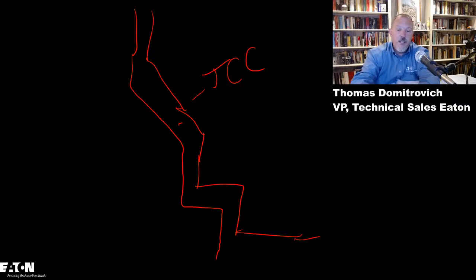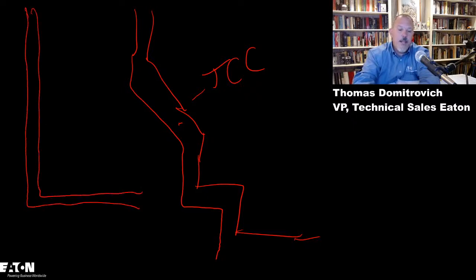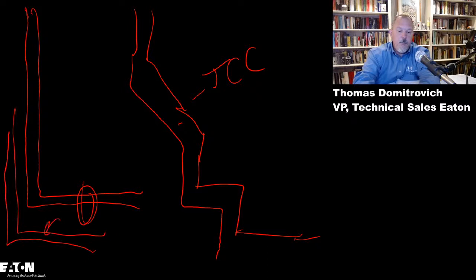Ground fault currents, if this is say a 200 amp feeder, your ground fault currents are going to be in the milliamps. You're never going to trip a circuit breaker upstream. The ground fault curves, I call them a hockey stick. Sometimes you'll have an I squared T in there, but for this discussion let's just say we have a hockey stick. When we say in that text that it can be coordinated, that means that I can actually add some intentional delay to permit the downstream ground fault protection devices to trip first. So this may be my GFPE down at the receptacle in that standard thermomagnetic circuit breaker. That's the residential type molded case circuit breaker, the small miniature stuff.